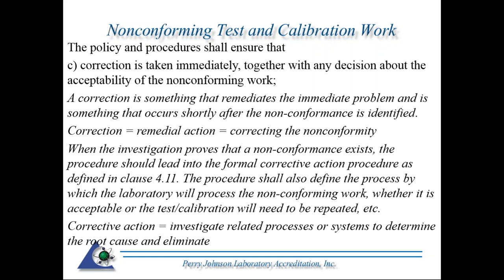We're going to look at an example a little bit later, so I'll go through the requirements now, and hopefully we'll clarify what the immediate correction is, as opposed to, if needed, what the long-term corrective action would be. So when the investigation proves that the nonconformance exists, the procedure should lead into the formal corrective action procedure as defined in section 4.11. The procedure shall also define the process by which a laboratory will process the nonconforming work, whether it is acceptable or the test or calibration will need to be repeated.